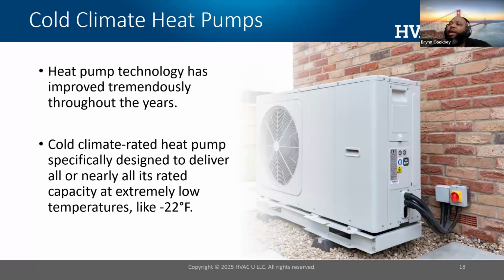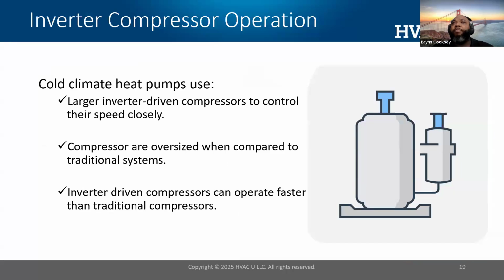Now, we have cold climate heat pumps. These cold climate heat pumps are awesome, in that they can deliver all or nearly all of their capacity at really low temperatures. Some manufacturers even market that they can deliver all their capacity at really extreme temperatures like -22, so that in any part of the country we can use a cold climate heat pump to deliver comfort.